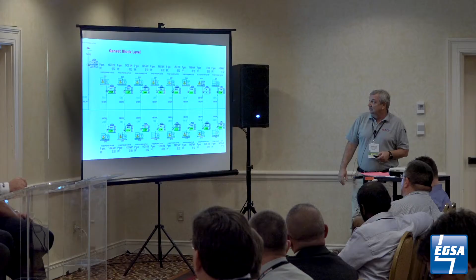This is just a heads up of one of our engines. This is a Caterpillar 3516B, where we're doing turbocharger diagnostics. We have a custom screen done in our data analytics program, and we're trending data over time. We're looking at intercooler temperatures, oil pressures, oil temperatures, and the power output of the machine, and we're doing that across multiple engines at the same time. All of that is being done in real time. We're not using any human intervention. We teach the data historian program to look for these parameters and generate a work order in our maintenance system if something goes out of specification.